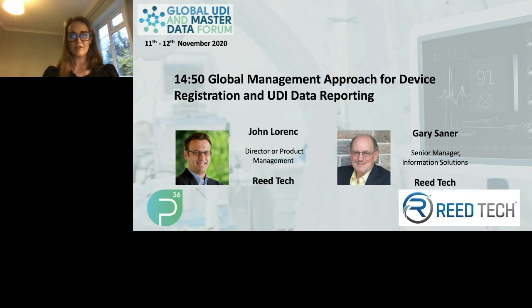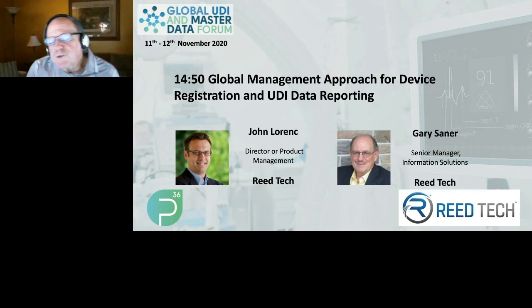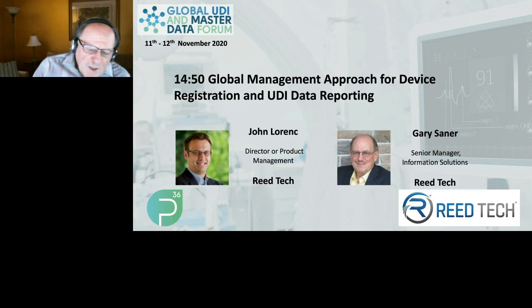Do we need UDI for integral drug device combination products? Yeah, so let me answer that first of all from the FDA point of view. There are some very nuanced rules about how UDI is applied to combo products. So in some cases, if the combination product has the assembly, the high-level combination product itself was reviewed, and the primary mechanism of action was a device, then CDRH would have been the approving and reviewing department. And in that case, UDI would apply at the very top level.